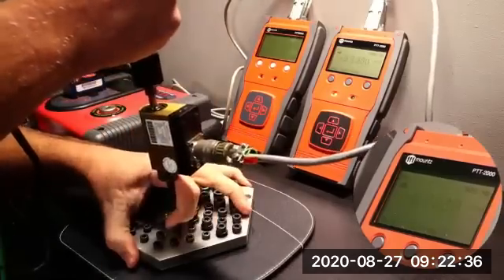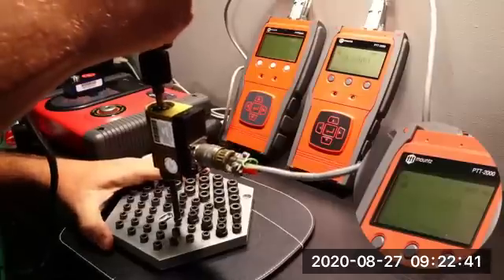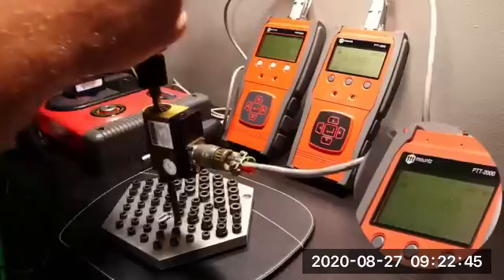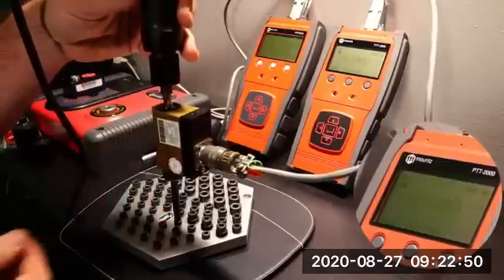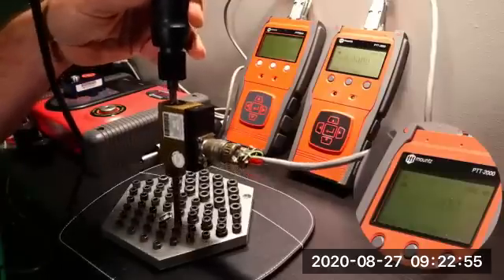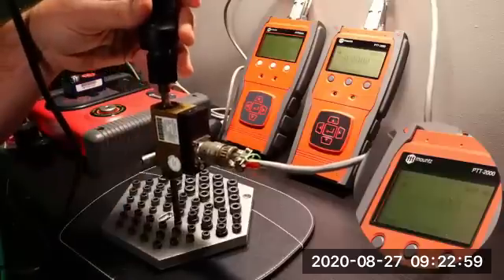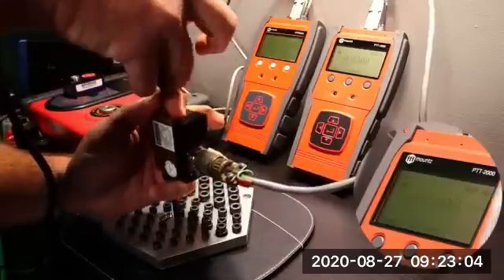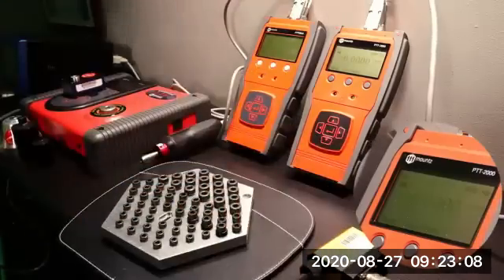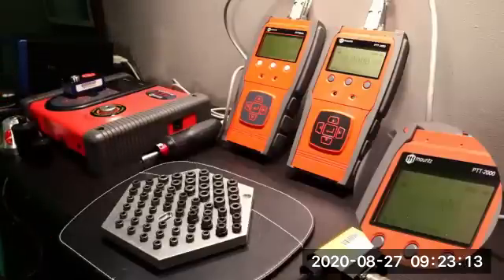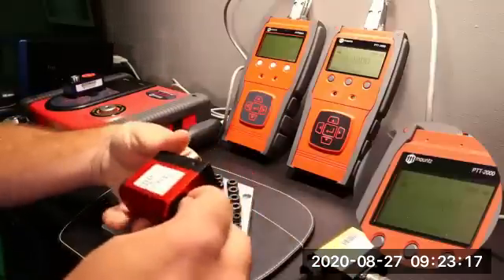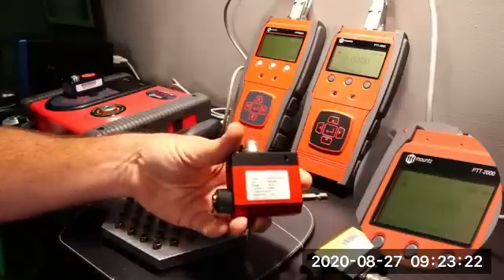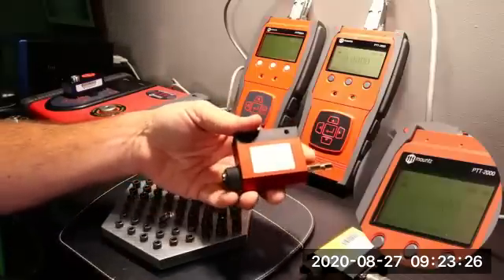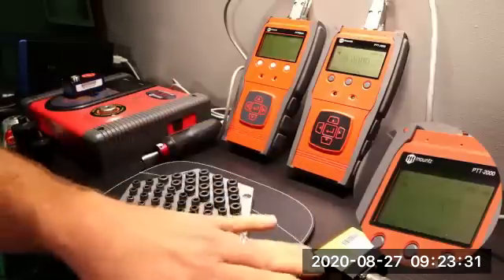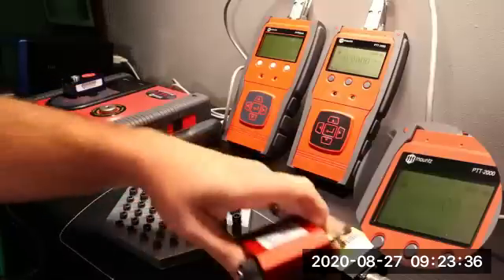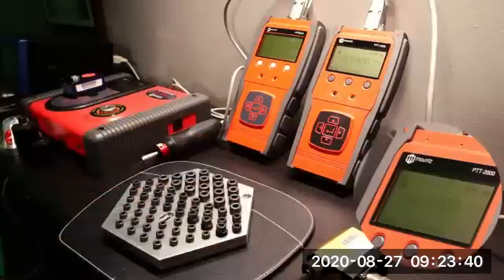I'll pull the fastener up, and then run it down. And now we get our torque value. So we're testing our tool on our application with the use of the rotary transducer. Again, this can be helpful for determining a torque value to make sure the joint characteristics are aligned with your joint simulators. If you also wanted to constantly monitor your output for your application, this would be an example of the sensor used with our brushless sensor. Again, this is a maintenance-free item. Our regular RTSX product does have brushes on it, and we'll show you how that works coming up. And that's the rotary transducer.